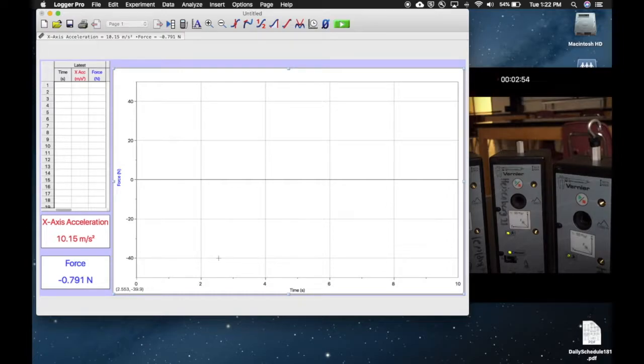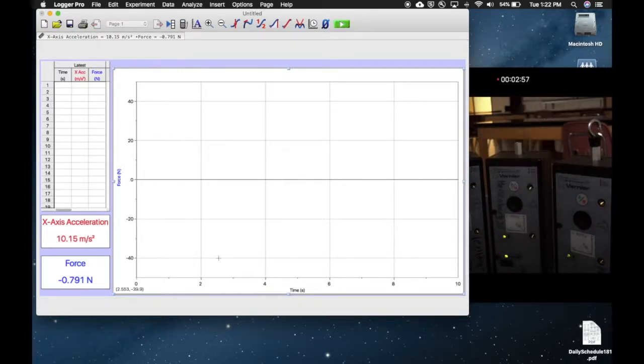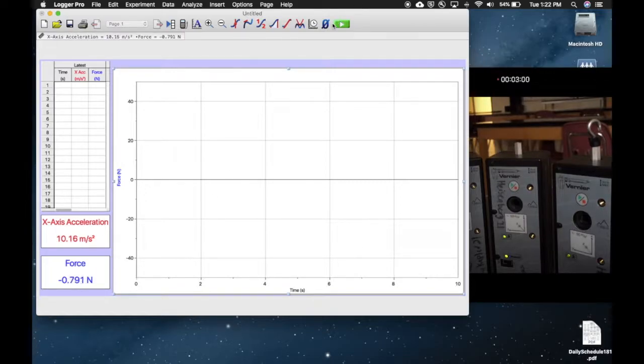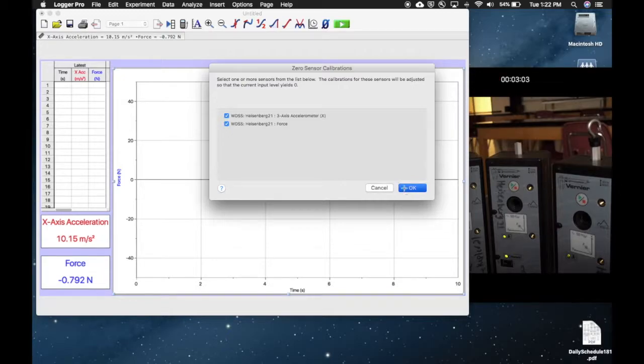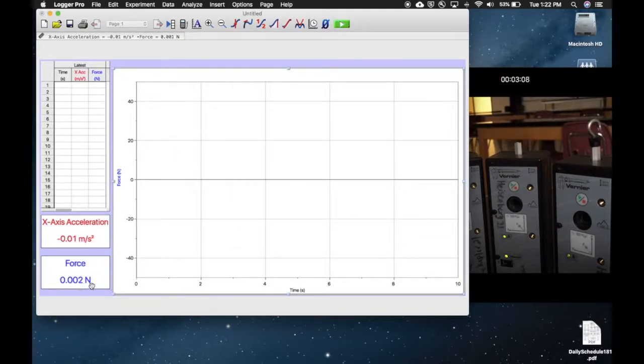Right now there's no force on Heisenberg - you can take a look there, there's nothing pushing on it at all, but yet it's still reading. So we're going to hit this big zero button up here. That's going to set everything back to zero. Hit OK, and you'll notice now that the force is going down much closer to zero.